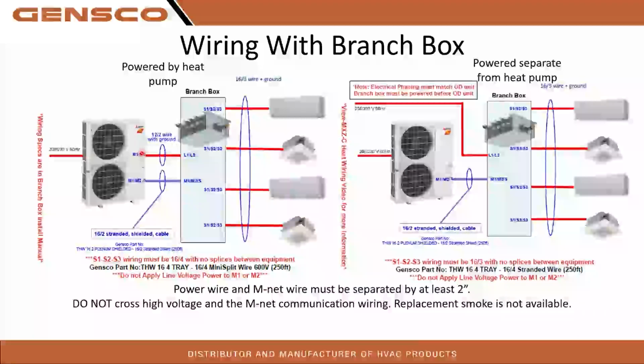So what'll happen is you'll send that high voltage AC to that low volt DC, because that's only 29 volt DC on this M1 and 2, and usually ends up blowing the board in the branch box. And if you do it real good, you'll end up blowing control boards, MNet power boards, or a noise filter board in your heat pump as well. So another great reason to not allow your electricians to run a 12/4 or a 14/4 wire for their power, because they will try to use it on M1, M2 and very likely cross those and blow up boards.